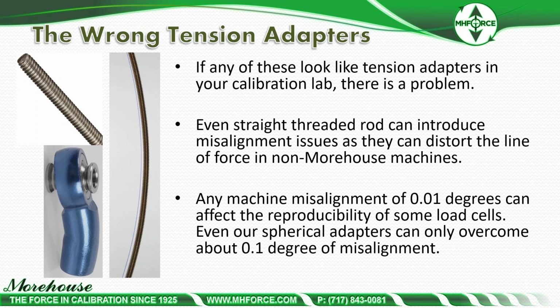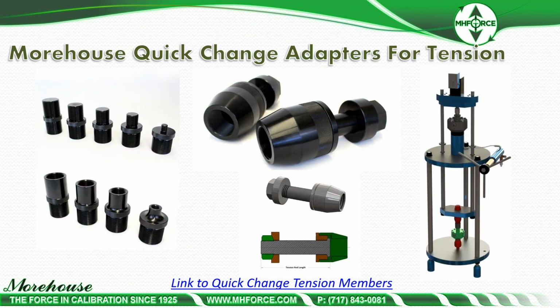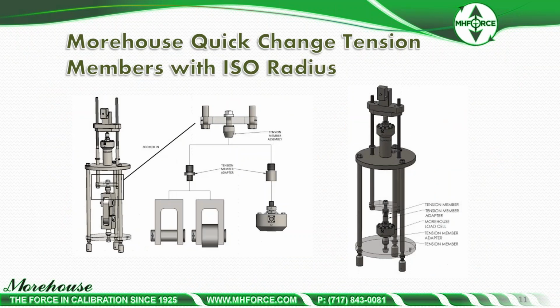Any misalignment of 0.01 degrees can affect the reproducibility of some load cells. With even our adapters, I said 1 degree, but we can definitely overcome 0.1 degree here. The 0.1 degree is the statement that we're standing by. The 1 degree is a bit of a stretch. But here we have quick change adapters for force. This is in line with lean principles, setup reduction principles. You have one set of tension members and then various adapters, which makes it real easy to couple load cells and the like. So it's an efficient process if you're having problems with setups.